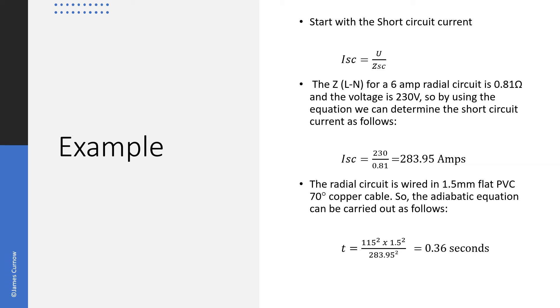What we're looking for here is for the time in seconds to be greater than the time that it would take the protected device to operate, because that would tell us that the cable is able to withstand that current for long enough for the protected device to operate.